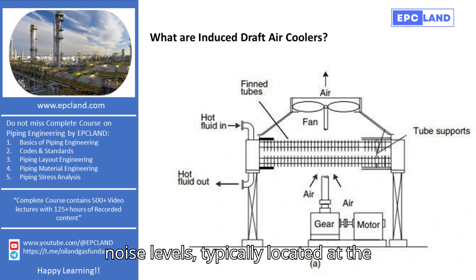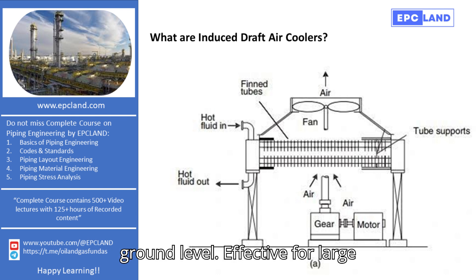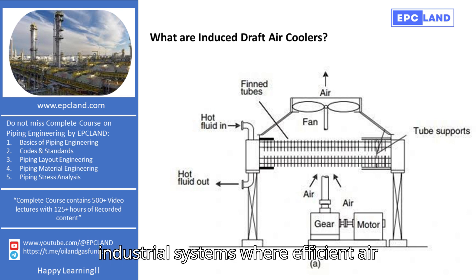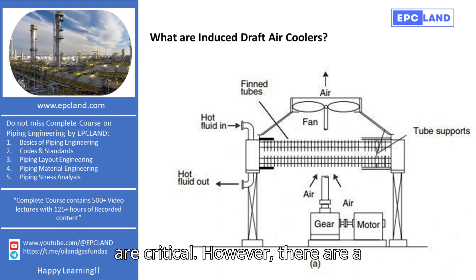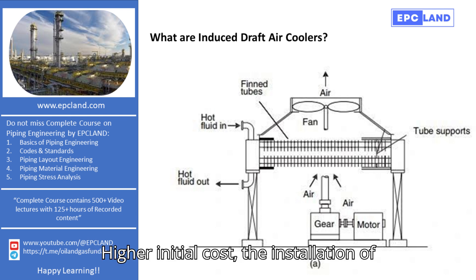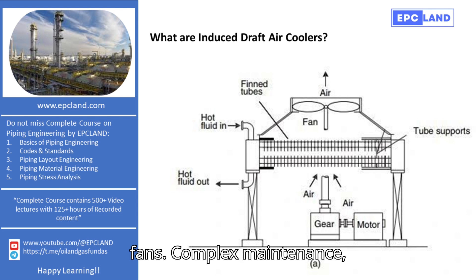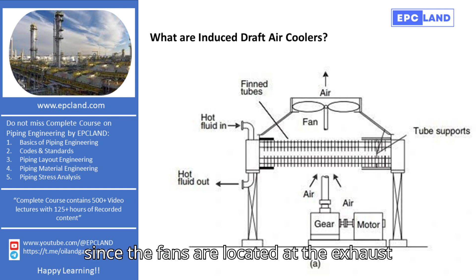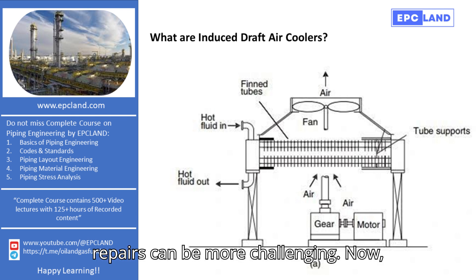Lower noise levels — typically located at the exhaust end of the system, induced draft fans tend to be quieter, especially at ground level. Effective for large systems — these fans are ideal for large industrial systems where efficient air movement and precise temperature control are critical. However, disadvantages include higher initial cost, as installation can be more expensive due to robust ducting and strategic fan placement. Complex maintenance — since the fans are located at the exhaust end or higher points, accessing them for maintenance and repairs can be more challenging.